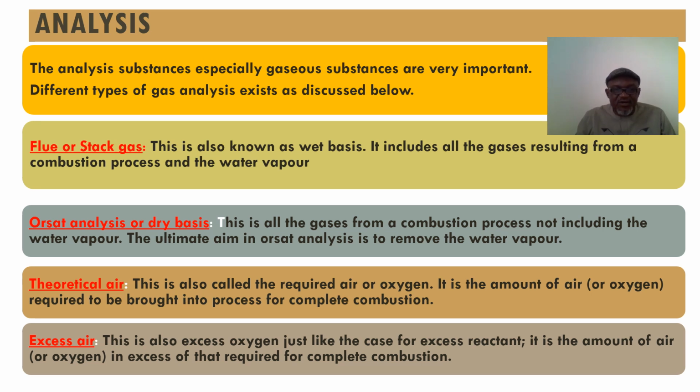Orsat analysis or dry basis. This is all the gases from the combustion process, but not including the water vapor. The ultimate aim in Orsat analysis is to remove the water vapor. Theoretical air. This is also called required air or oxygen. It is the amount of air required to be brought into process for complete combustion.